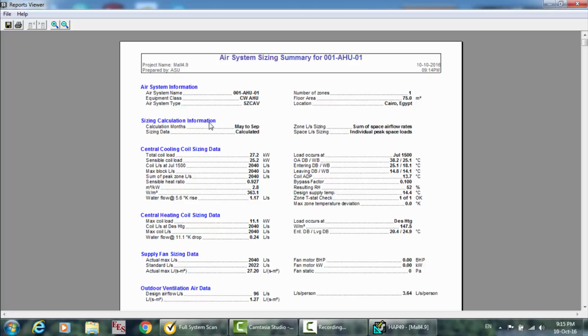Okay, sizing calculation information, the calculation months that we selected at the schedule or at the system, from May to September. Sizing data calculated. Zone liter per second sizing. Notice that here the units are SI units, and I'm going to show you in the next couple of minutes how to make it in CFM and ton refrigerant. Here is the space liter per second sizing, sum of space airflow rates, and space liter per second sizing individual peak space load. The central cooling coil sizing data, all of these. The total coil load is 27.2 kilowatt.